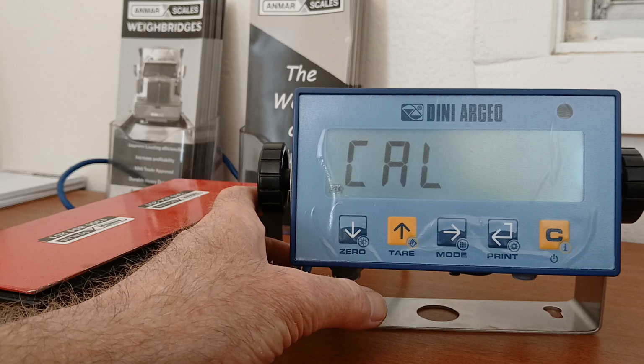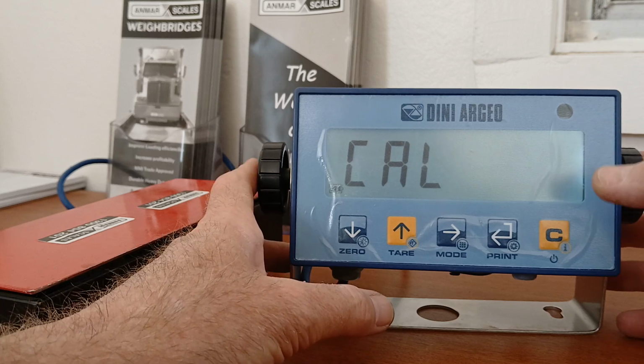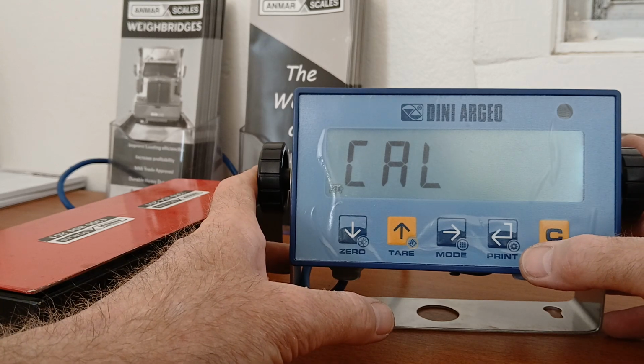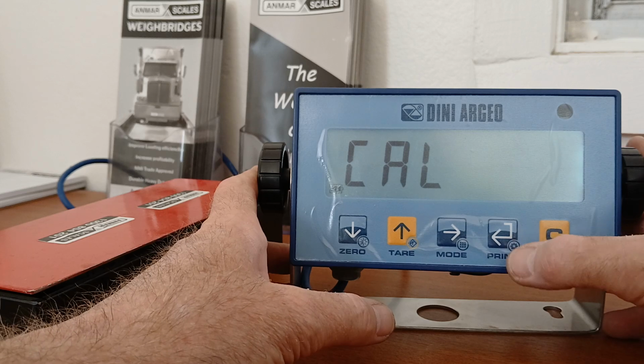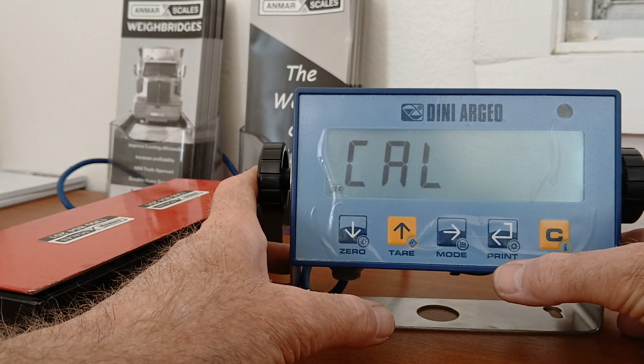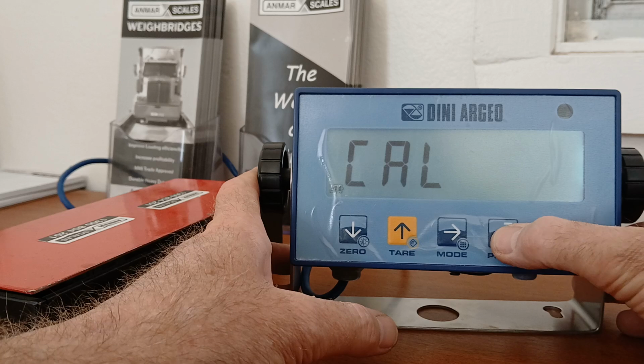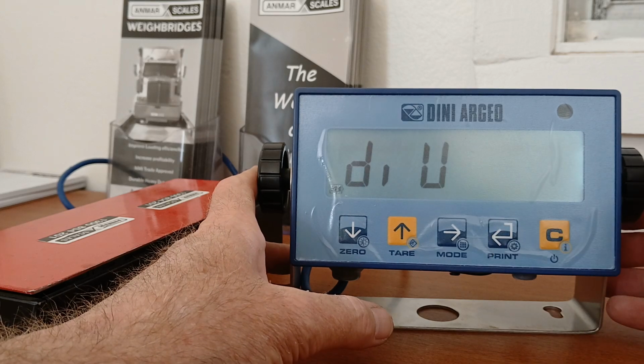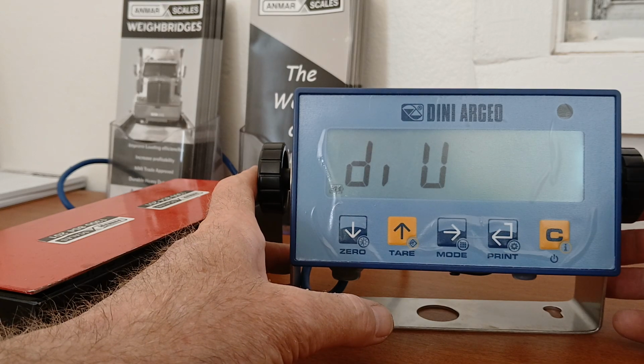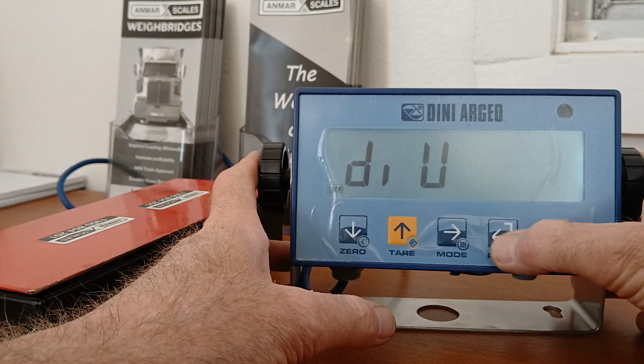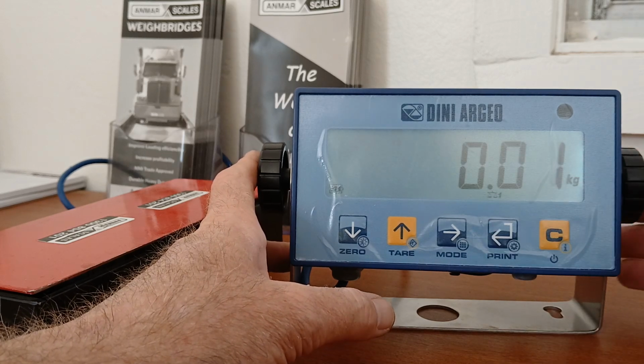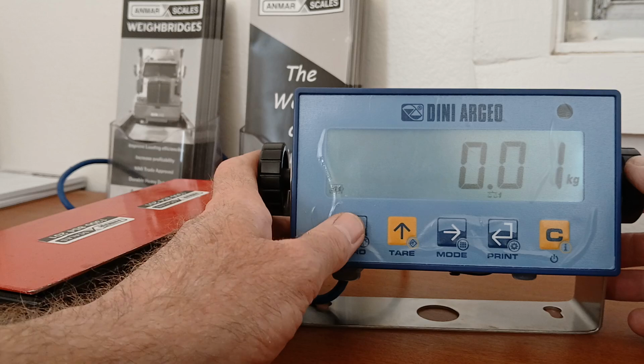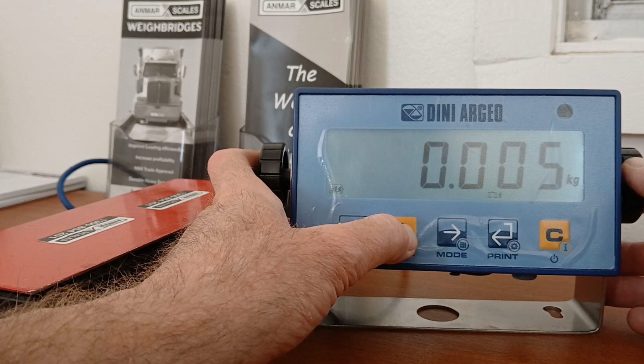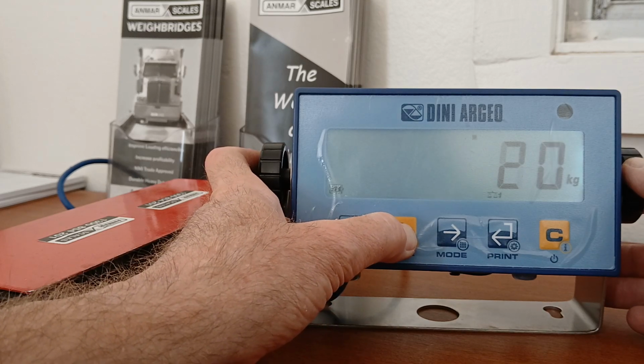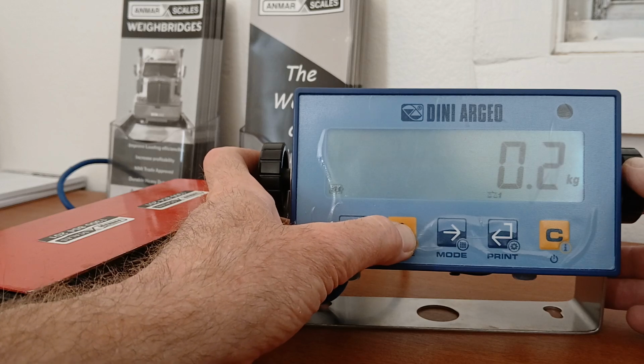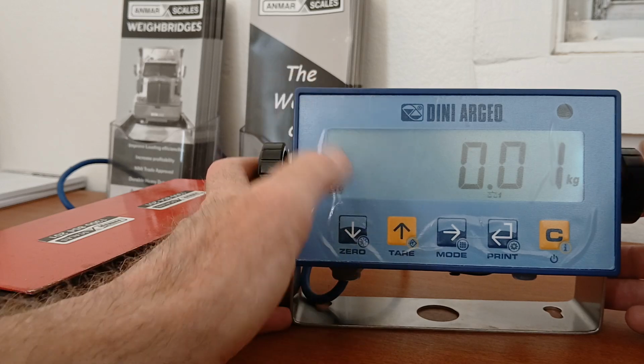So it flashes tech and then goes to cal. That's the calibration setup, where we set the scale capacity, division, and we actually do the zero and span calibration. By pushing the enter print button, the scale will display div, which is your scale division or increment. If we select that with the enter button, it shows you what the scale is set to already. Pushing the up and down arrow, you can change the division and the decimal point. I'm going to set this up as 30 kilos by 10 grams, so we'll leave it there.